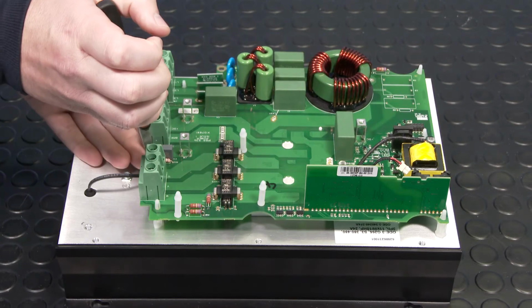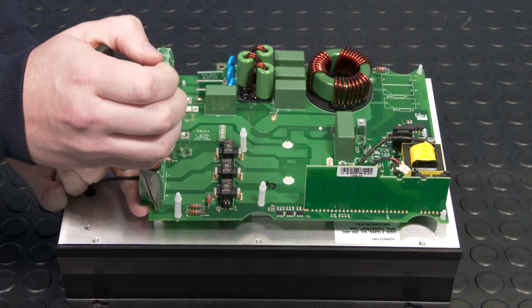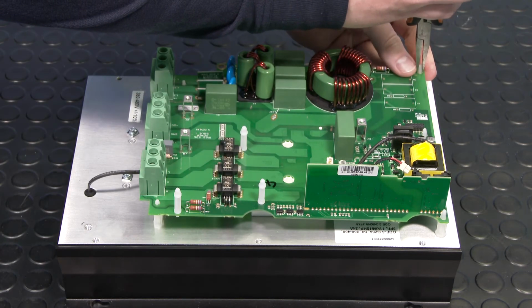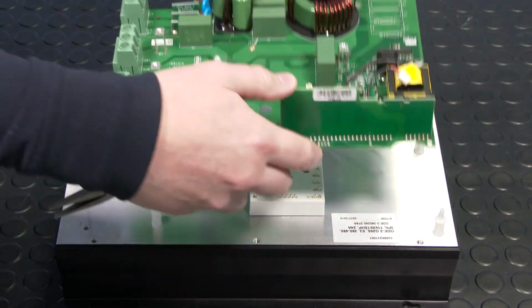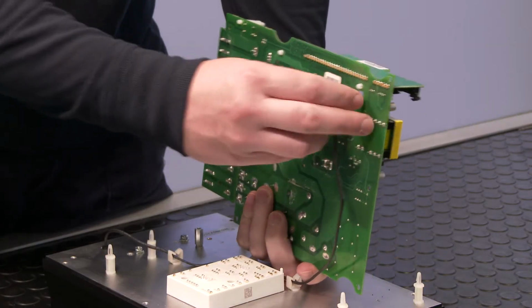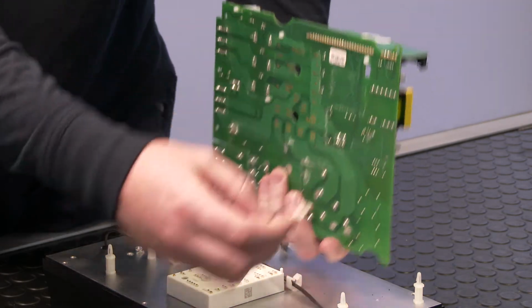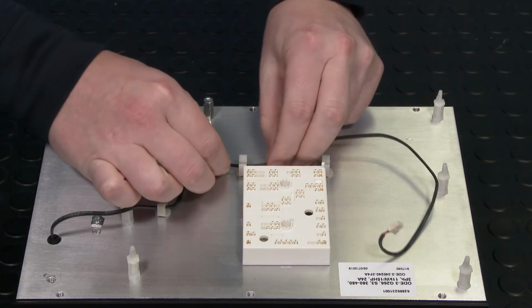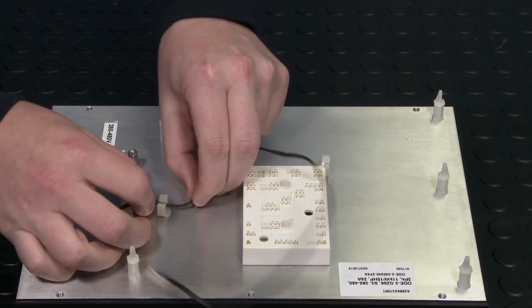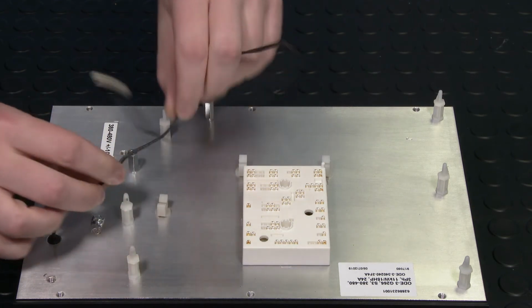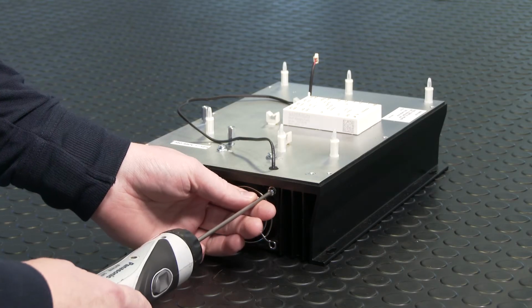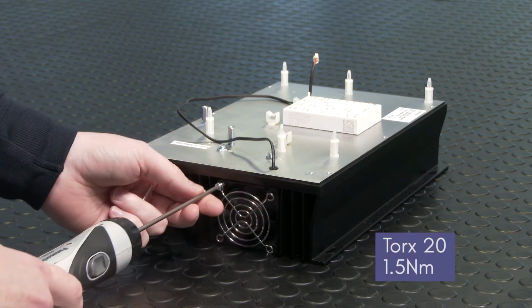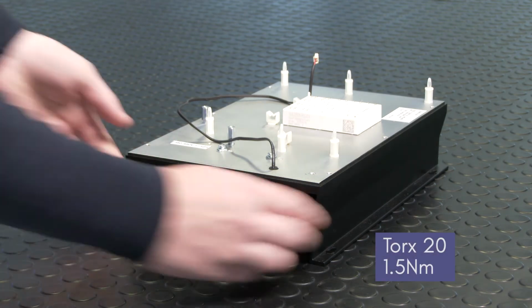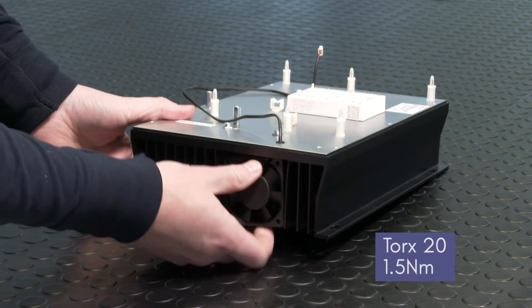Using long nose pliers, unclip the 6 plastic pillars from the PCB and lift it away, making sure the power module stays in place and the power board is placed on a clean surface. Unclip the fan cable from the 3 fan cable clips. Use a Torx 20 screwdriver to remove the 2 fan screws and remove the fan from the heatsink. The torque setting is 1.5 Nm.